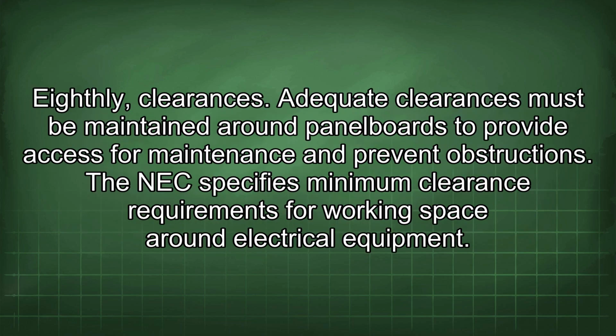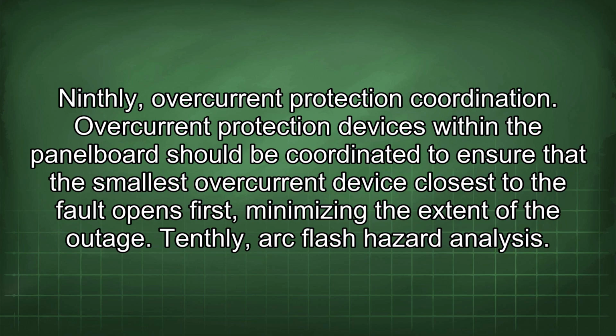Eighthly, clearances. Adequate clearances must be maintained around panelboards to provide access for maintenance and prevent obstructions. The NEC specifies minimum clearance requirements for working space around electrical equipment. Ninthly, overcurrent protection coordination. Overcurrent protection devices within the panelboard should be coordinated to ensure that the smallest overcurrent device closest to the fault opens first, minimizing the extent of the outage.